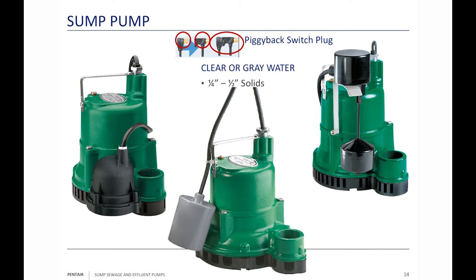Pumps are tested for about a million cycles, while switches run around 350,000 cycles, so you could easily go through two or three switches during the life of a pump. Just because the pump doesn't work doesn't mean you should throw it out — sometimes you just need to check if it's the switch causing the problem.